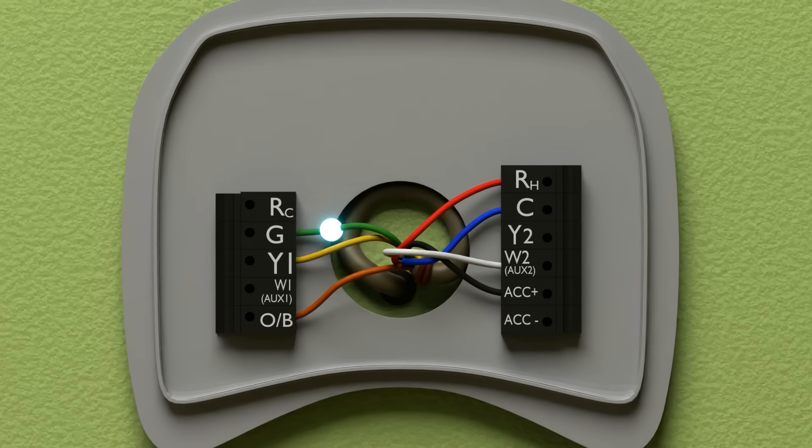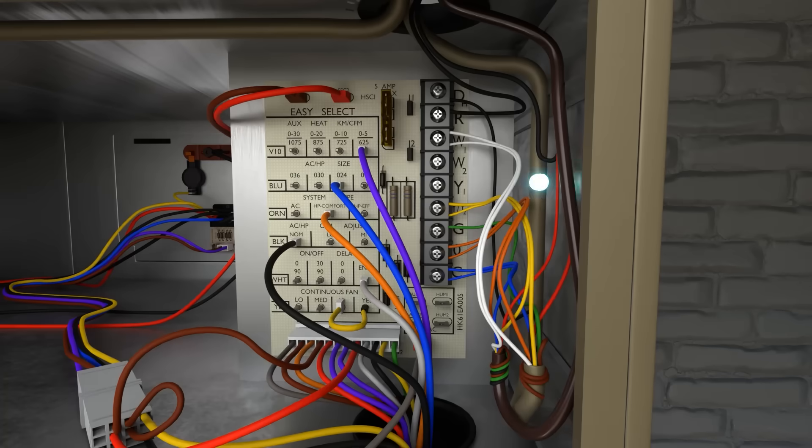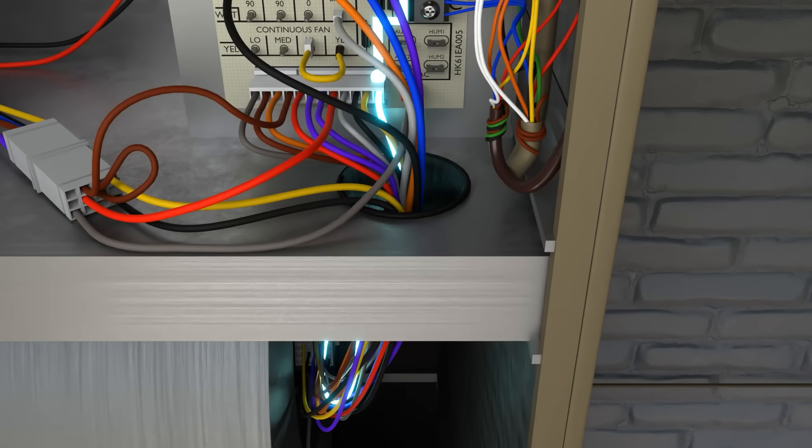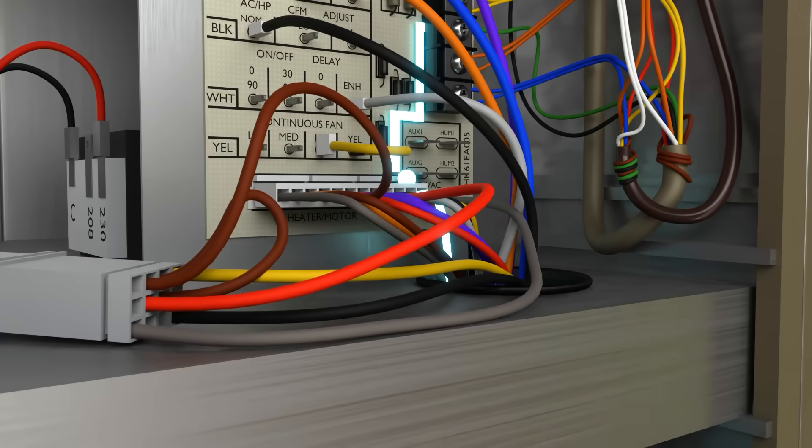Next, we have the G terminal. The G terminal is for a constant 24 volt power applied to our blower. Keep in mind that many variable speed blower motors will not come up to speed unless 24 volts is applied on G during cooling mode. As you can see, this feeds down to the blower motor and brings the blower motor on. This is used especially during the constant fan on setting on the thermostat.